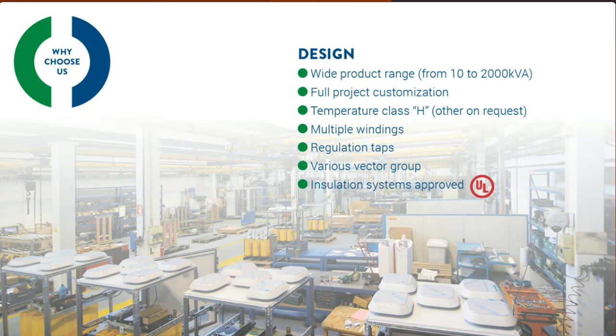Moving then from the design stage to manufacturing, we have the production capacity to manufacture anything that is being designed by us. That includes the windings with different materials like aluminum and copper, the magnetic core that can be made by different materials. As a standard, we use thinly laminated steel sheets, but on requirement, we can also use oriented grains, the insulated materials. But then we are also very careful about our environmental impact. So we use an impregnation with polyester resin to reduce this type of impact, and the baking process that is completely internally controlled.